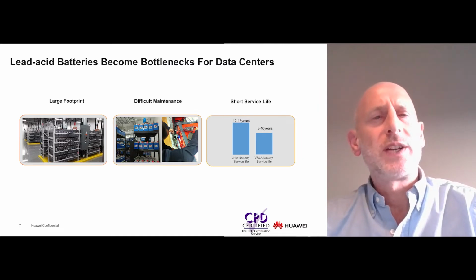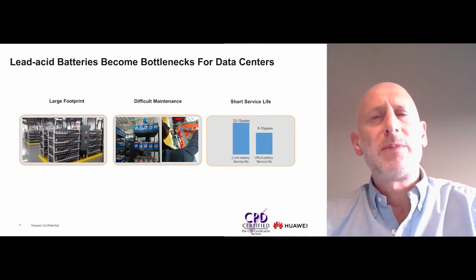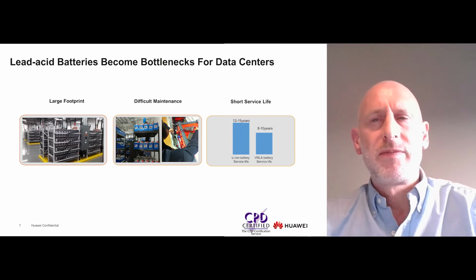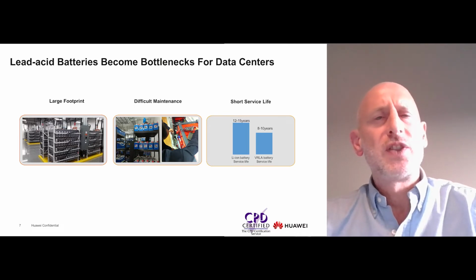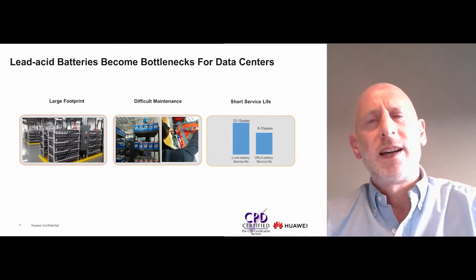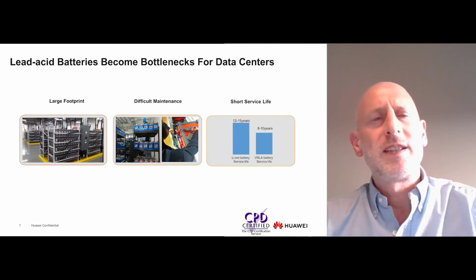Operation and maintenance can be challenging using lead-acid batteries. There are often strict operational requirements in various application scenarios, and the temperature must be stable. Only about 600 cycles of charging and discharging are supported, but charging and discharging must be performed periodically, and the speed must be moderate. For safety considerations, a separate battery storage room is required, and because of their size, the data center must be designed with floor space and weight bearing in mind.